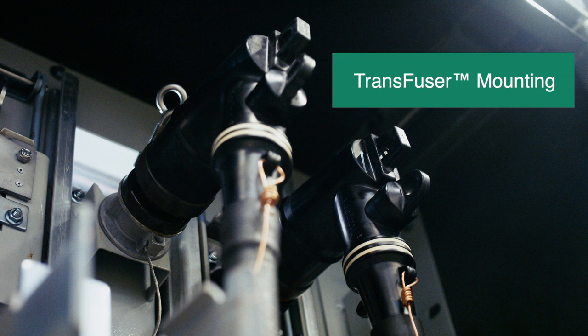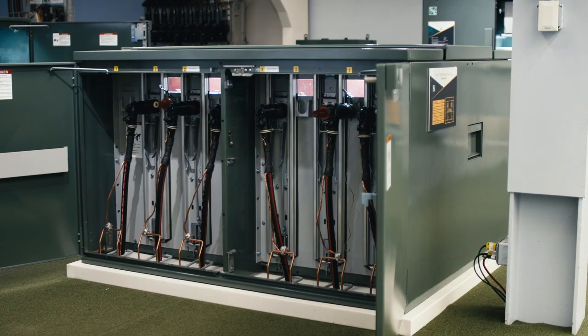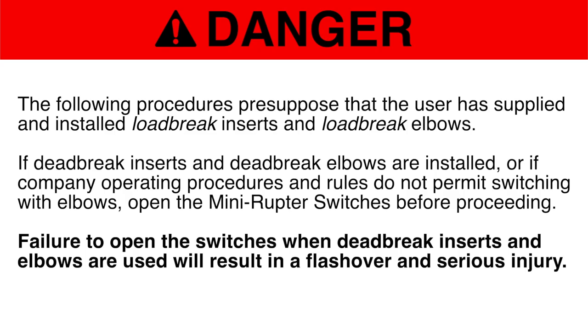S&C Manual PME pad-mounted gear is equipped with a unique transfuser mounting, a fuse handling mechanism that is interlocked with the loadbreak elbow. Danger: The following procedures presuppose that the user has supplied and installed loadbreak inserts and loadbreak elbows. If deadbreak inserts and deadbreak elbows are installed, or if company operating procedures and rules do not permit switching with elbows, open the Mini-Rupter switches before proceeding.